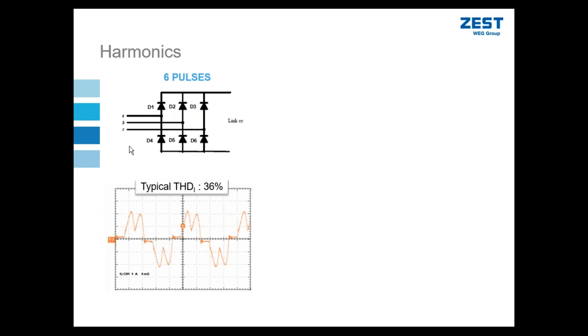The higher the load, the lower the total harmonic distortion as a percentage. We saw that the waveform got less distorted because it's drawing more of the current from the supply, less of the current from the capacitor. At low load scenarios, my distortion as a percentage of my current is much higher. However, because my load is low, the actual absolute amplitude of that current is less. So it has a lesser effect on distorting the voltage.